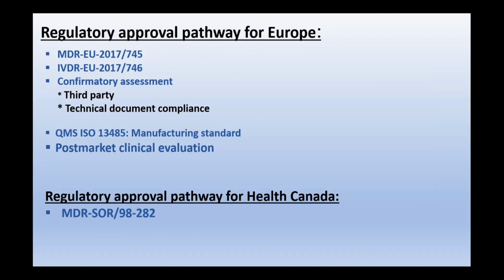Along with that, the manufacturer also has to undergo conformity assessment by a third party and technical documentation compliance. The quality management standard ISO 13485 has to be followed by the manufacturing organization. Post-market clinical evaluation is also performed on the same devices by the manufacturer and the regulatory authorities.